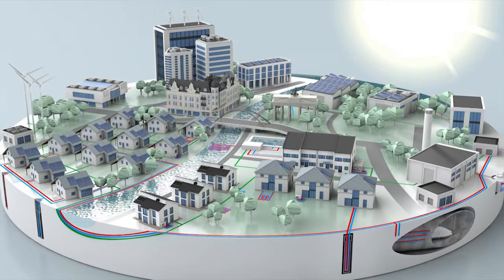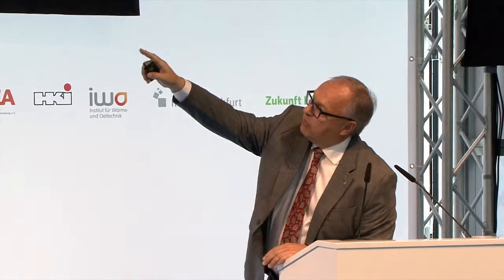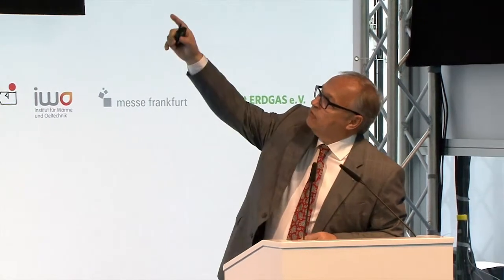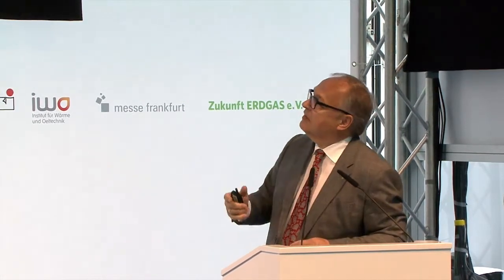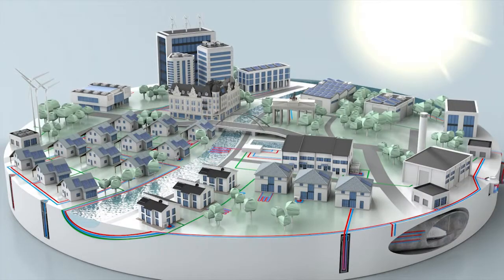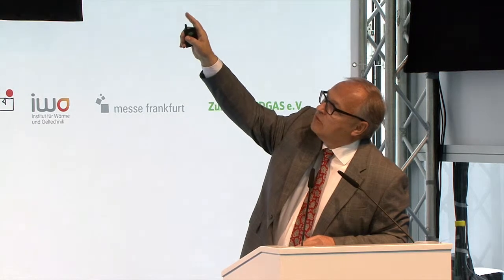You see the multi-story building, the original building supplied with a heat pump using water. At the front, new one-family dwellings use heat exchangers and wells in the front field. The river flowing through the town also provides heat extraction — the so-called surface water. There are subway ducts where wastewater can be used for the heat pump, and to the right you see an ice storage that can be used artificially. So we use the new buildings, the old buildings, the high-rise buildings and hotels, and also industrial zones in the rear of the picture.